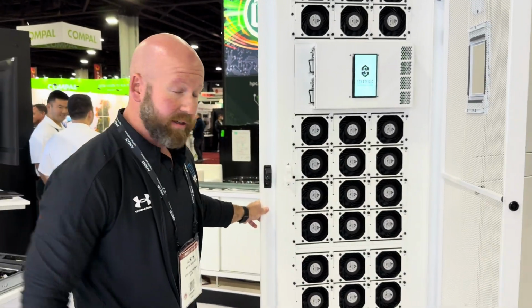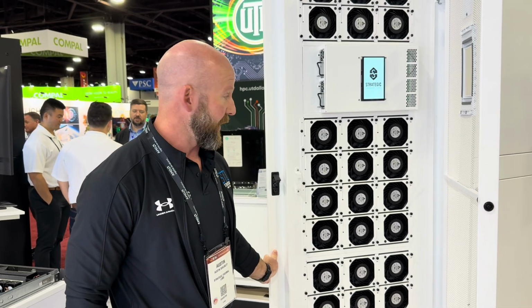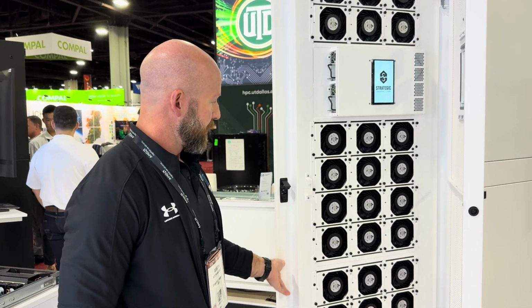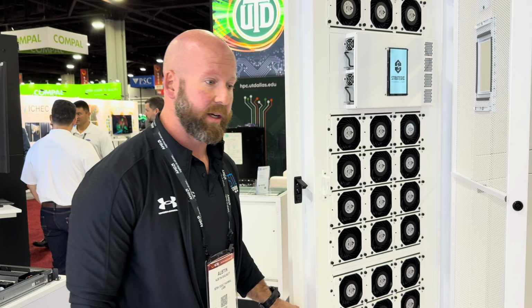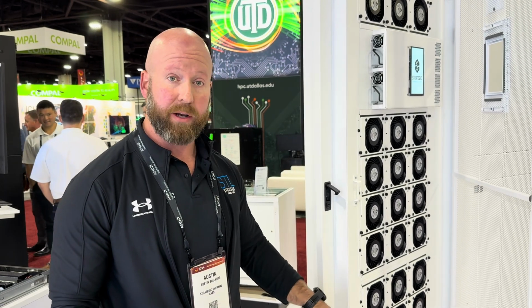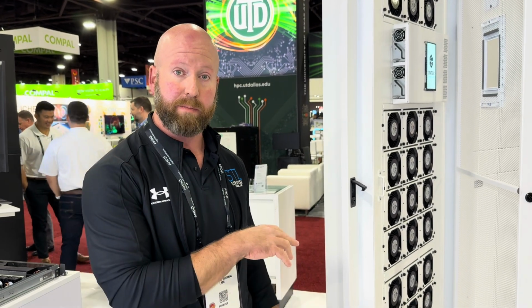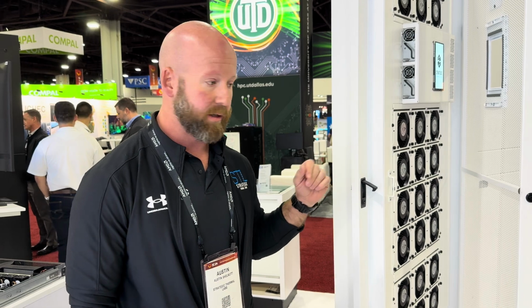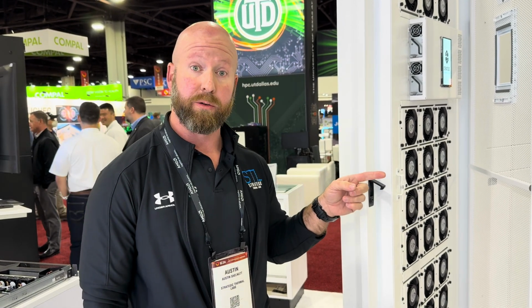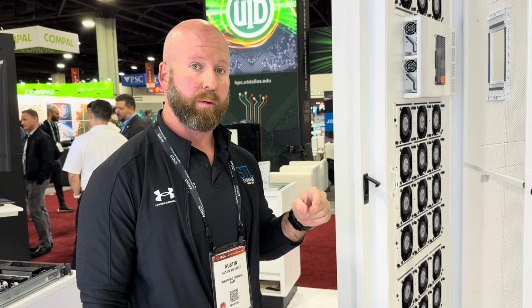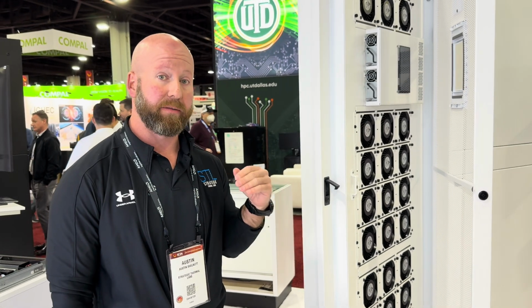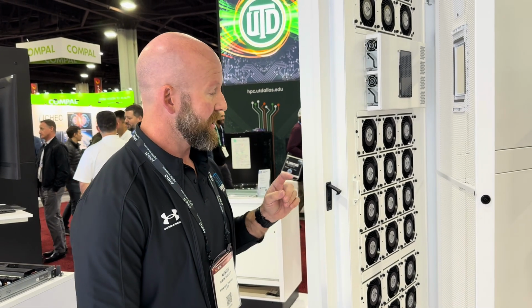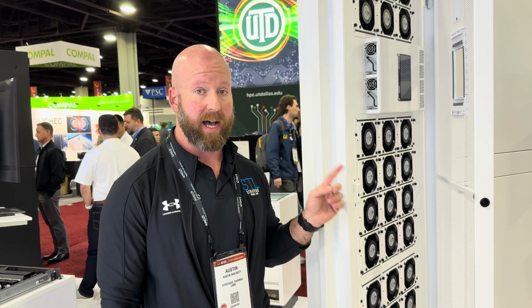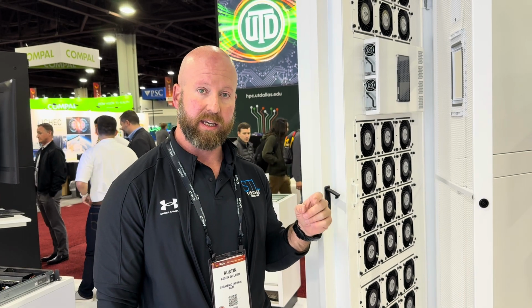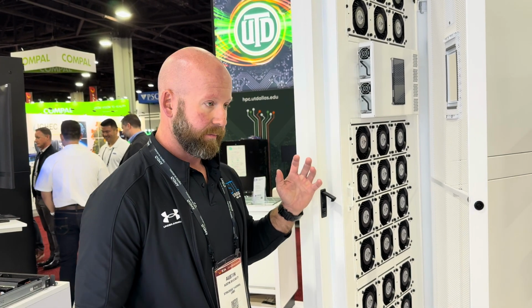This is 36 120 by 38 millimeter fans operating at 48 volts. That provides us a number of advantages, but it turns out when you try and do a parametric optimization of the coil impedance, the server impedance, and the ability to push airflow through the door, we wind up operating at a much higher mechanical efficiency point by using DC axial fans than what is possible to achieve with an EC blower.